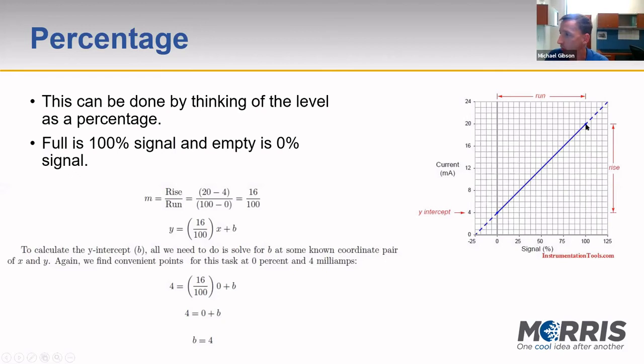So at 20 milliamps, we are 100% open. At 4 milliamps, we are 0% open, or closed — in this case, the water level is 0. And the water level is completely full at the other end of the scale.